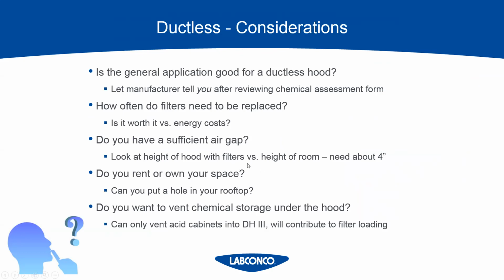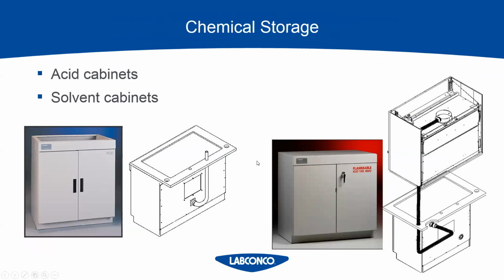And here's an image of how these cabinets vent into the fume hood. If you are ducting out, you can vent a solvent cabinet connected to the ductwork above. Once again, this has to be negatively pressured duct, so it has to be with the remote blower setup, not a built-in blower setup. And the acid cabinet on the left shows how those are vented in the fume hood with a connection through the work surface. You can do that with a DH3 or any ducted hood, and the solvent cabinet on the right has to be ducted with a remote blower.